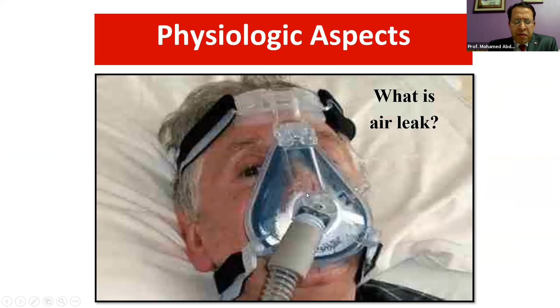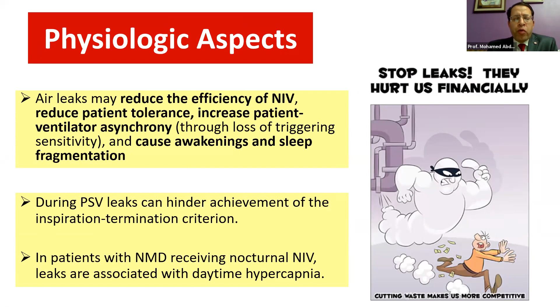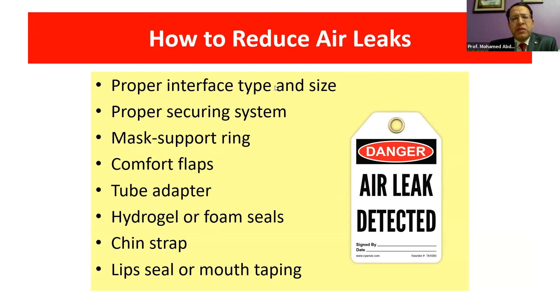So when you stop air leak, you are going to maximize the comfort for the patient and the function for the machine in order to avoid what's called air hanging, because if the patient continues to escape the air beneath the mask, the machine will not sense that inspiration is terminated and will continue giving tidal volume, what's called inspiratory hanging. So we have to tighten the mask, with proper interface type, proper securing system, mask support ring, comfort flaps, tube adapter. We have to apply what's called the foam or hydrogel, chin strap, lip seal or mouth taping. All of these measures reduce the air leak.